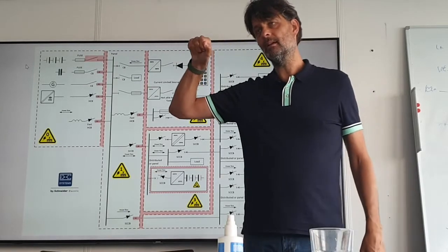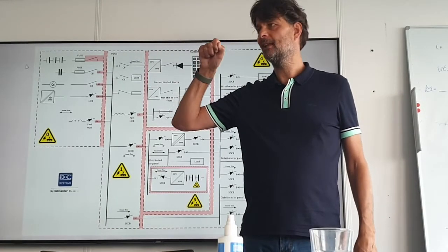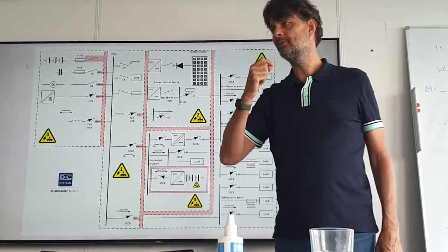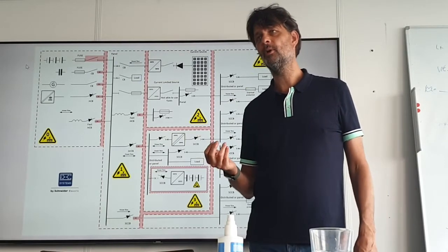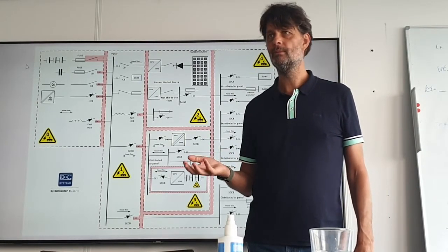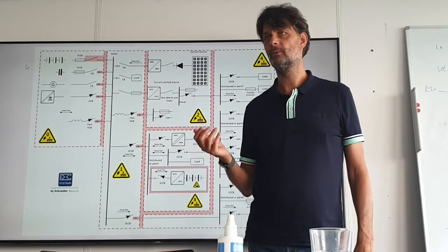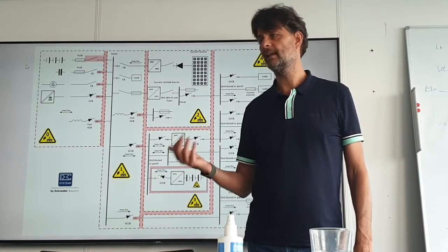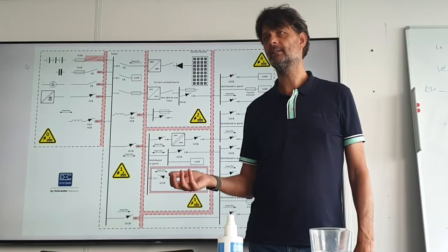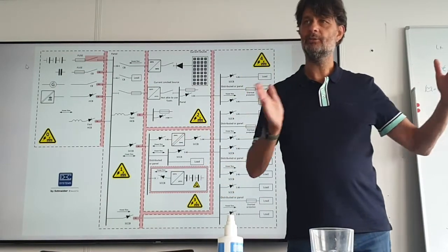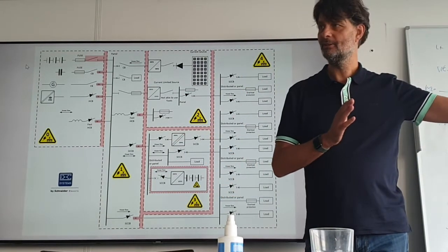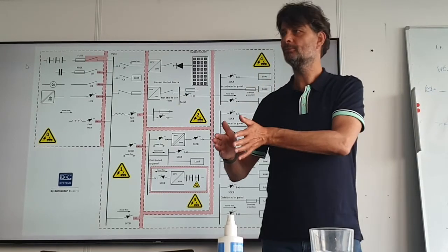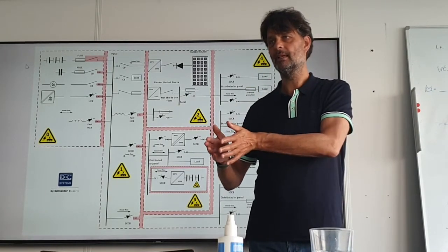And they tried to make earth fault conditions, and it was reacting all the time. So even with an earth impedance above 1 kilo ohm, 2 kilo ohm, we could still protect it as a protected measurement inside the timing. So then they really said, okay, we have an installation of 3.5 kilometers with RCD functionality, and even with a not properly connected PE, we still have a reaction.